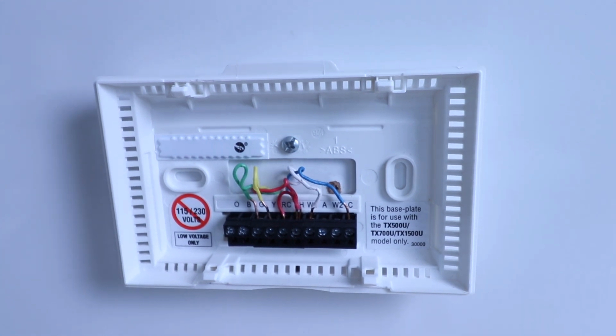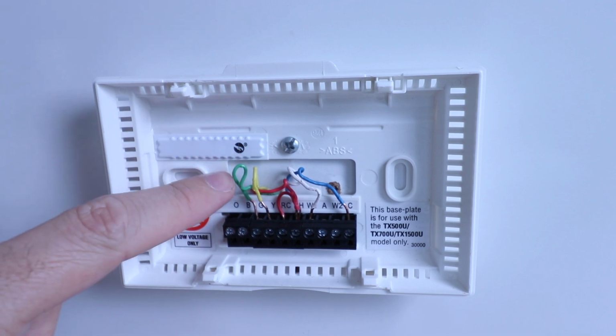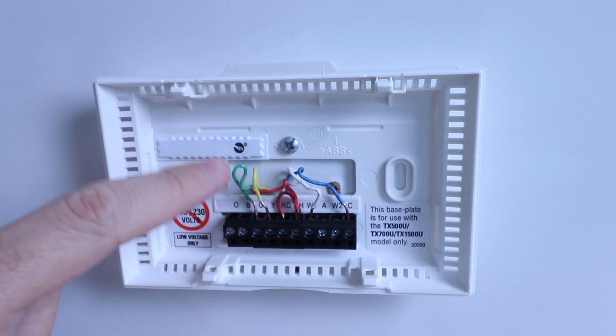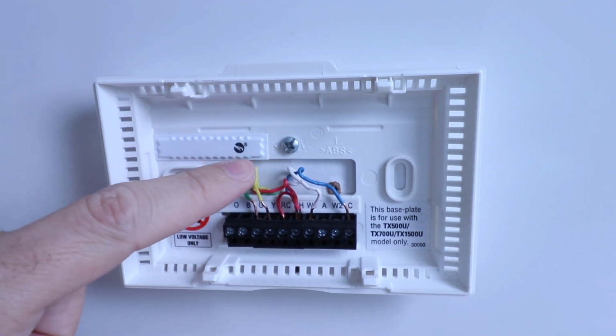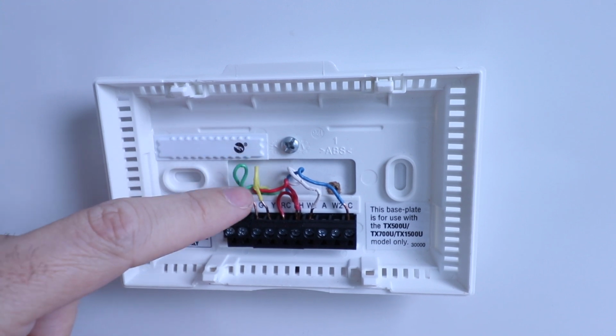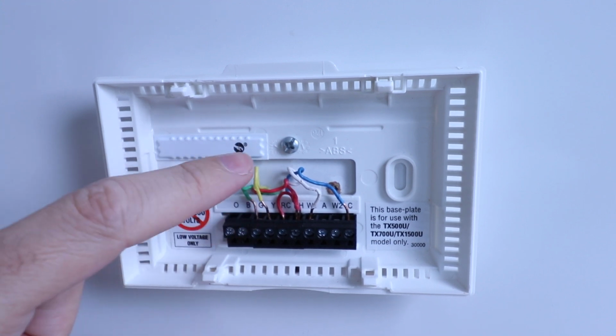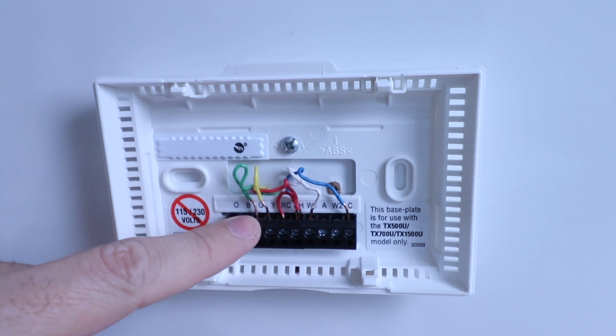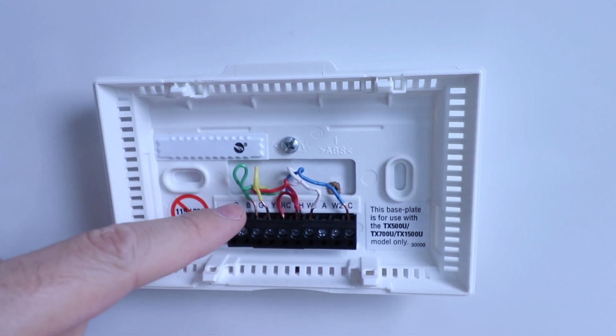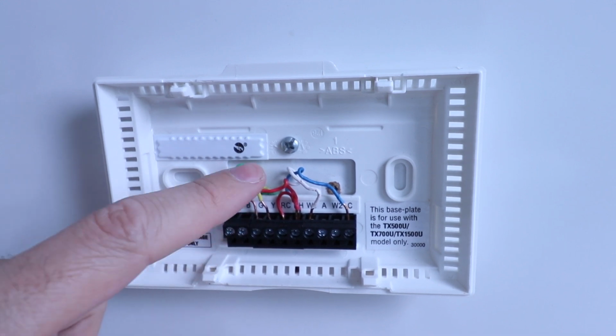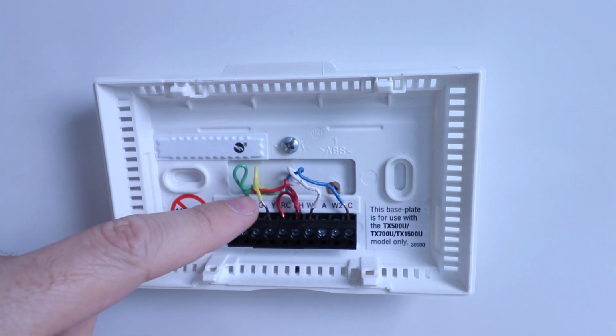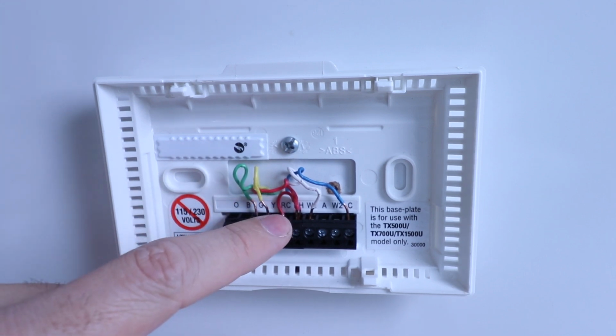We've got our G wire here, which is our fan wire, and that's a green wire. The next wire we have is our Y wire, our air conditioning control, and that's yellow. It matches up with Y, and you can see these letters matching the colors, G for green, Y for yellow. The next wire we have is our R wire, wired into the RH terminal, and this is our red wire.